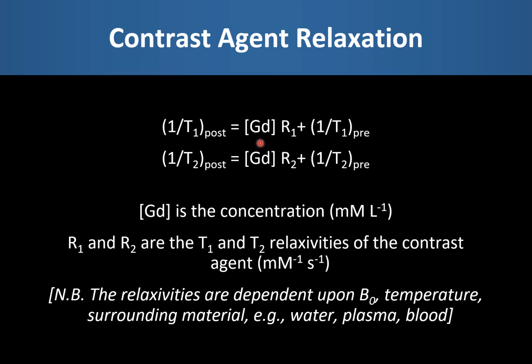To a good approximation, the change in relaxation rate, which is 1 over the relaxation time, is directly proportional to the contrast agent dose at clinical levels, and we have this proportionality constant, which is the relaxivity of the contrast agent itself. So we have equations for both T1 and T2 following administration of the gadolinium contrast agent, but because T1 is substantially larger than T2, the effect on T1 is much bigger, plus the fact that a reduction in the T1 relaxation time wherever the contrast agent affects water molecules in that vicinity will result in a signal hyperintensity, whereas a reduction in T2 on a T2 weighted scan will simply cause a signal hypointensity.